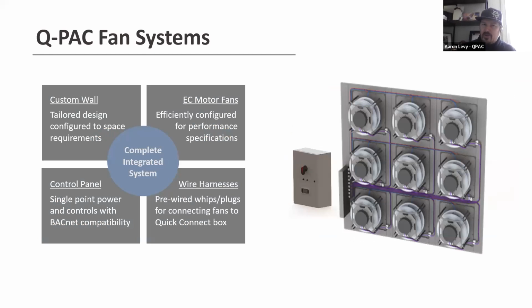We provide you pretty much everything you need to install the system. That includes the custom bulkhead. So what we ask is you measure floor to ceiling, wall to wall, CFM, static pressure, voltage, and then we can build a space for that. The bulkhead comes in hand carryable pieces. We also provide you with the motors themselves, all the wiring harnesses that go with it, all the controls, the outdoor display and main disconnect, as well as the quick connect box or boxes inside, depending on the number of fans.